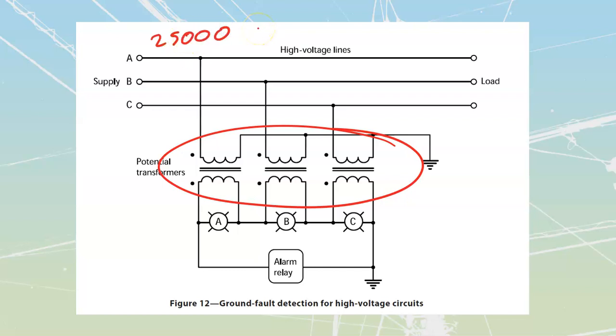If this is 25,000 volts, I have a PT connected across, forming a star point, a neutral point with that one. What we'll have is phase value of voltage across here, so I don't have to insulate as high. It's going to be 14.4 kV across there. On the other side, my PT is a 14.4 kV to 120 volts, so it's going to place 120 volts.